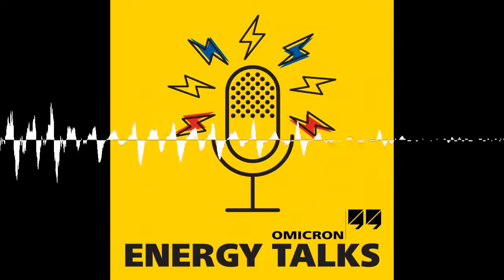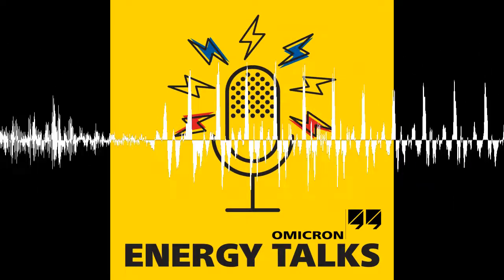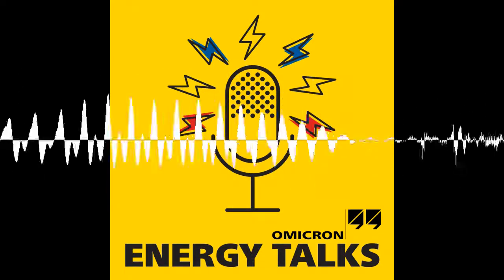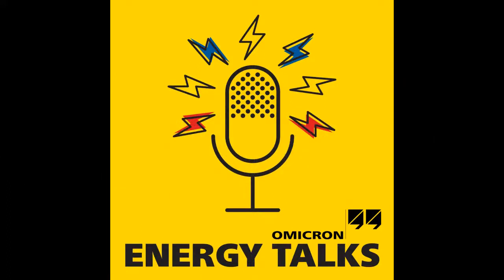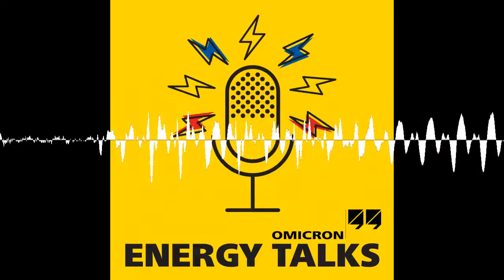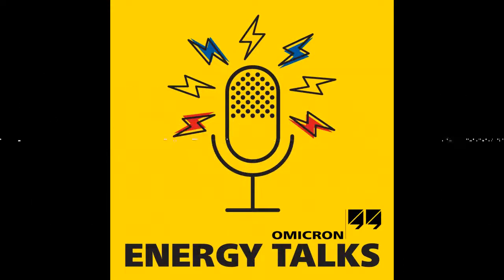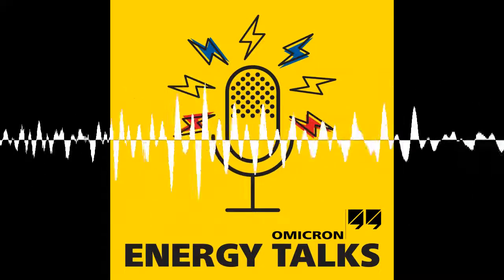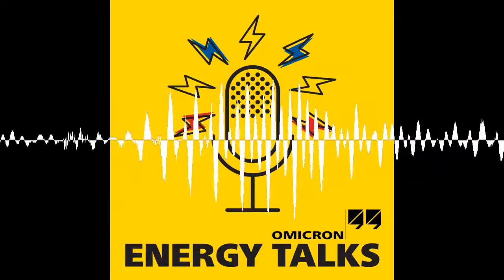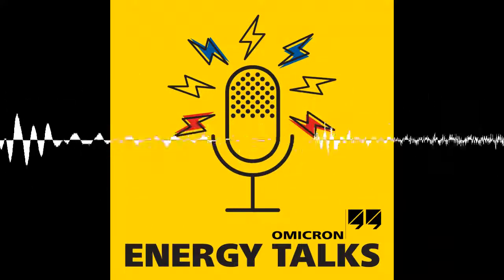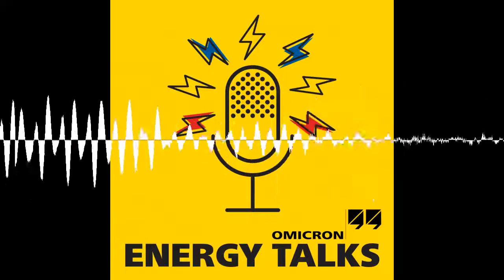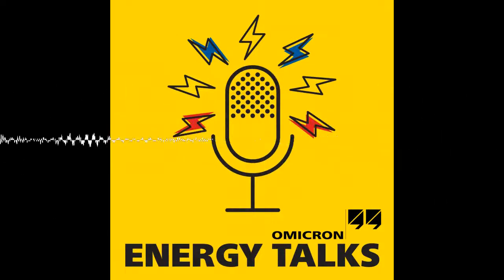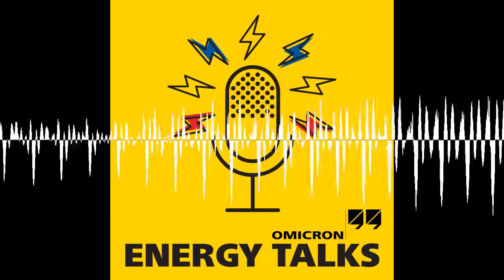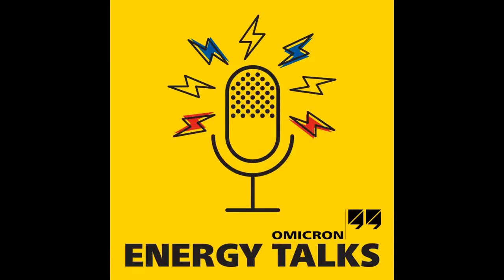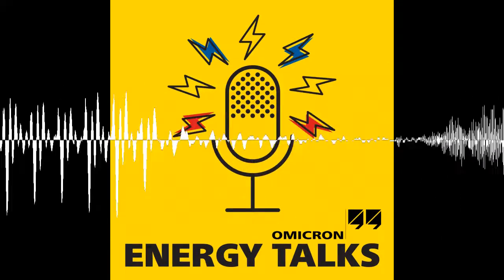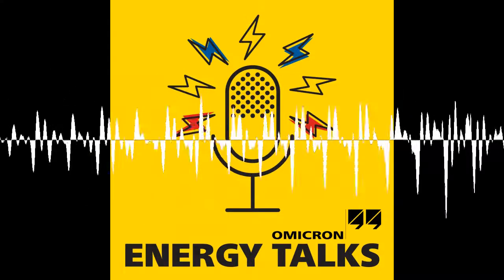Could you please describe what an earthing or grounding system is? For example, what does it consist of? Why is it important? And what role does it play in the power system? Yeah, an earthing system has two main functions. First, it's responsible to reliably carry electrical currents into the earth. Such currents can flow during the normal operation of a system, for example, from the neutral point of a transformer, but they also will flow in case of a fault of a power electrical system. In this case, such currents can become very, very high, often in the range of 10 kiloamps and more. And a grounding system must be able to handle such high currents without exceeding any operational or equipment limits.